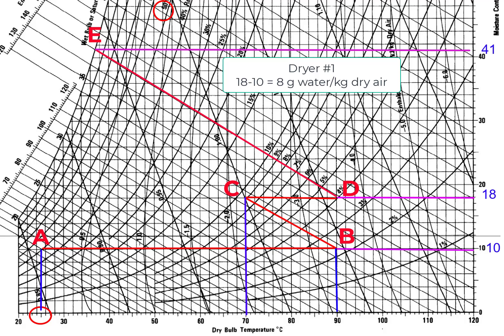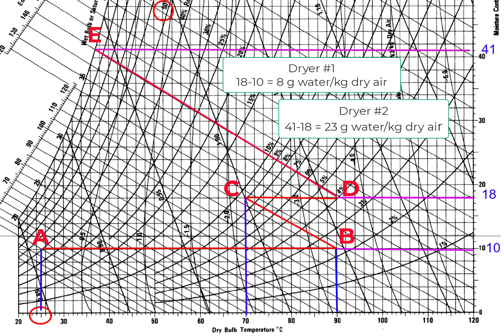The moisture removed in the first dryer is 18 minus 10, so 8 grams of water per kilogram of dry air. For the second dryer it will be 41 minus 18, which is 23 grams of water per kilogram of dry air. Those are the answers for this problem.